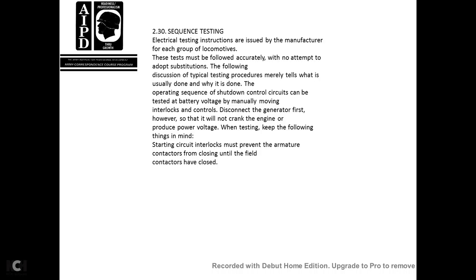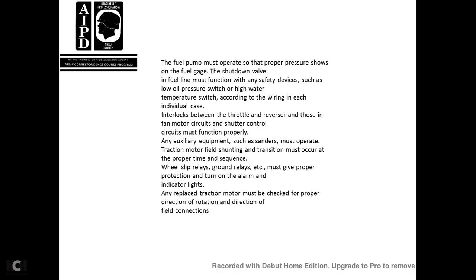Starting circuit interlocks must prevent the armature contactors from closing until the field contactors have closed. The fuel pump must operate so that the proper pressure shows on the fuel gauge. The shutdown valve in the fuel line functions with any safety devices such as the low oil pressure switch and high water temperature switch, according to the wiring. In each case, the interlocks between the throttle and reverser, those in the fan motor current circuits, and the shutter control circuits must function properly. Any auxiliary equipment such as sanders must operate. Traction motor field shunting and transition must occur at the proper time and sequence.